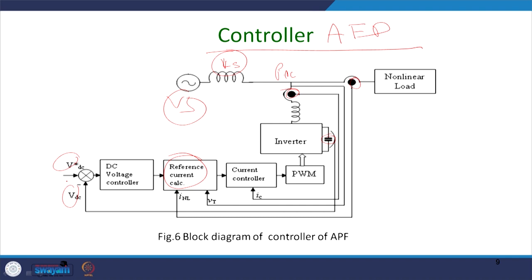Your DC bus voltage is required to be maintained around 20 percent higher than the peak value because if it is only compensating harmonics, the harmonic current is quite small, and due to that very small current flowing, this device will remain near its open-circuit voltage. But you have to actively take it around 20 to 25 percent higher than this voltage typically. We will see the different topological variations where you can have different advantages and reduce switching losses.